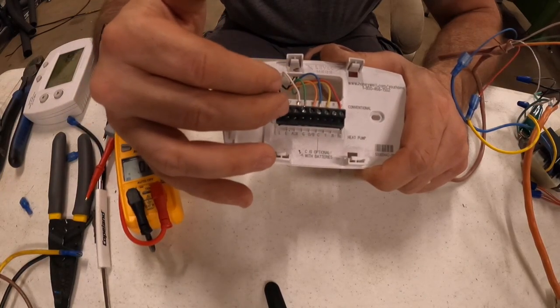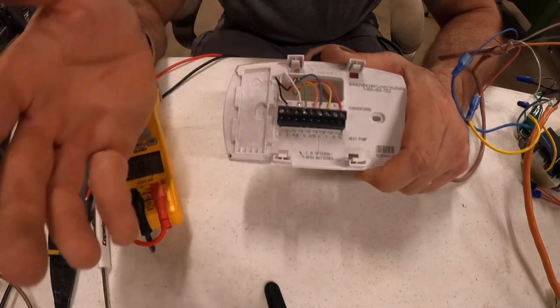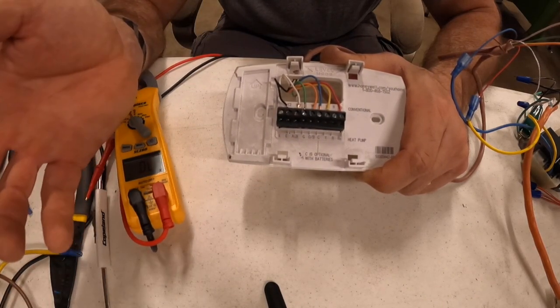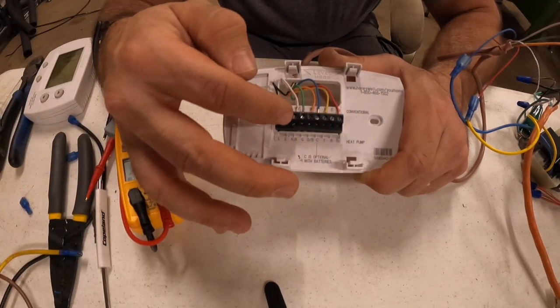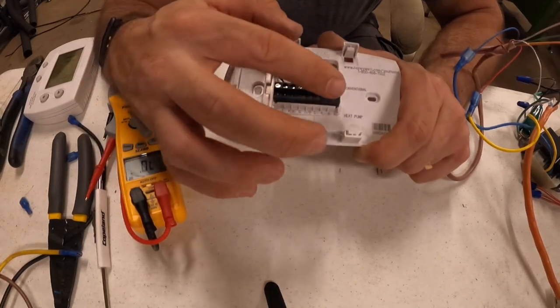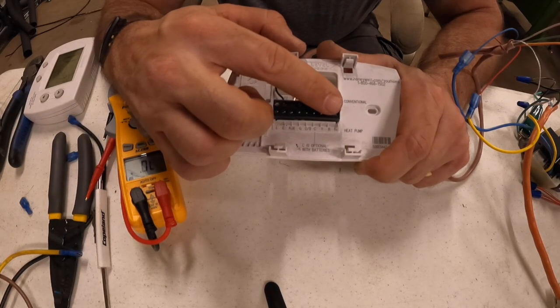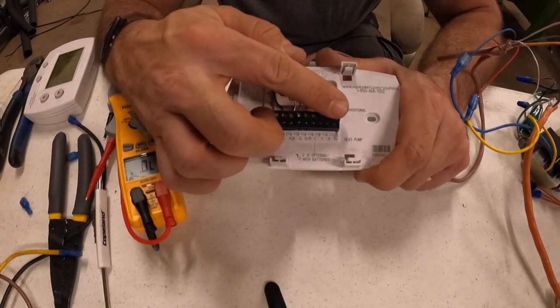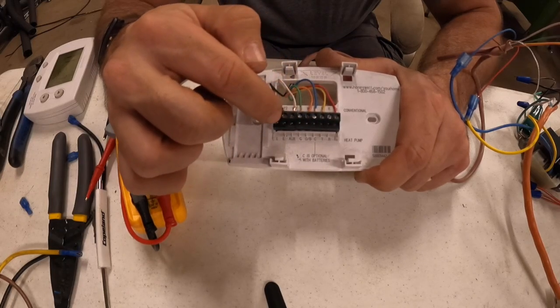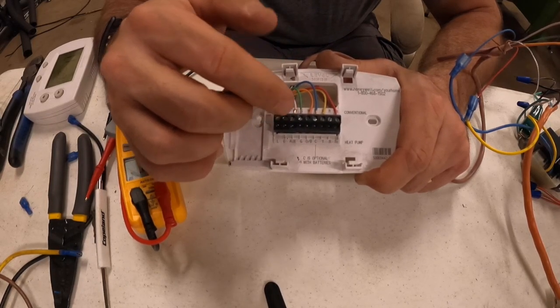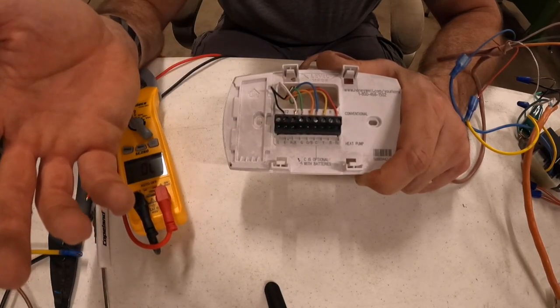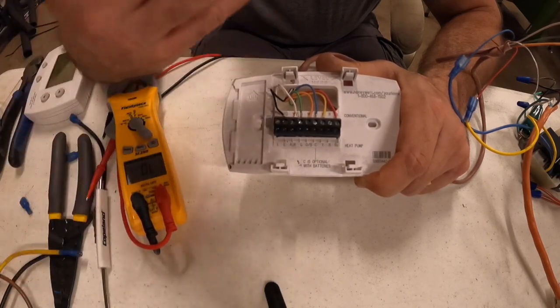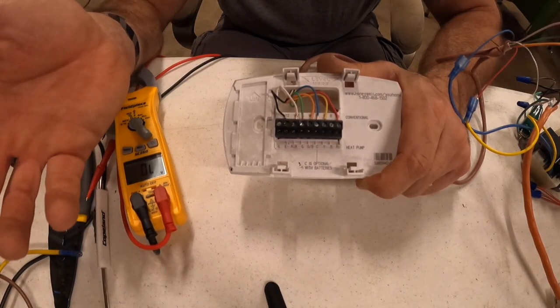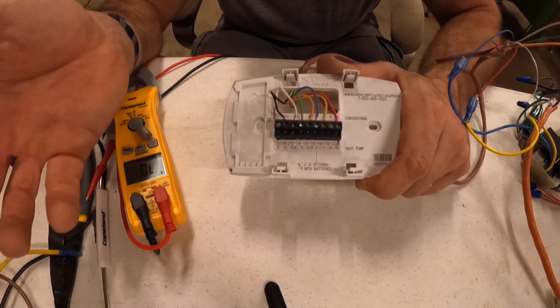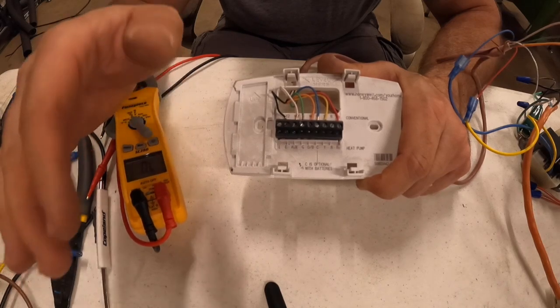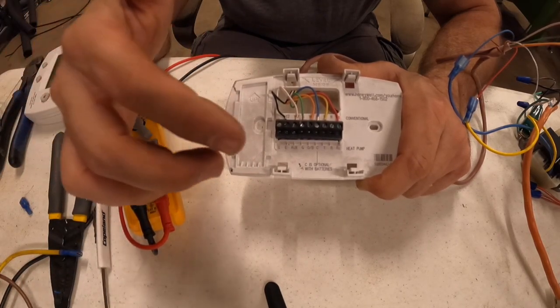And the principles of how this works are the same for a digital thermostat or analog, the old mercury style or the spring activated. There's always going to be wires that serve a purpose. So starting with R here, that's the 24 volts coming in from the transformer. So the thermostat takes that voltage and applies it to each one of these other terminals depending on what's being called for, whether you're calling for heat or cool, then you have multiple stages of heat and cool. You might have 2-stage cool, 1, 2, or 3-stage heat.